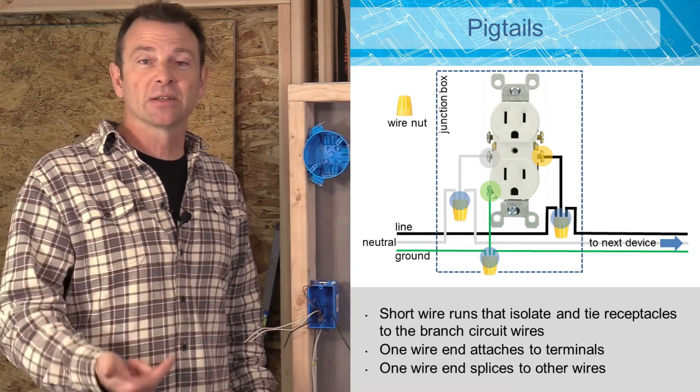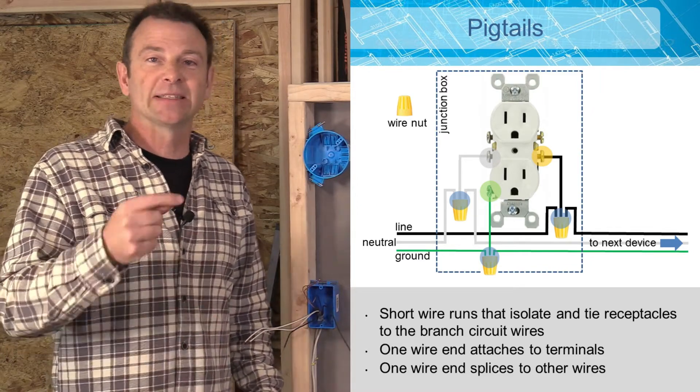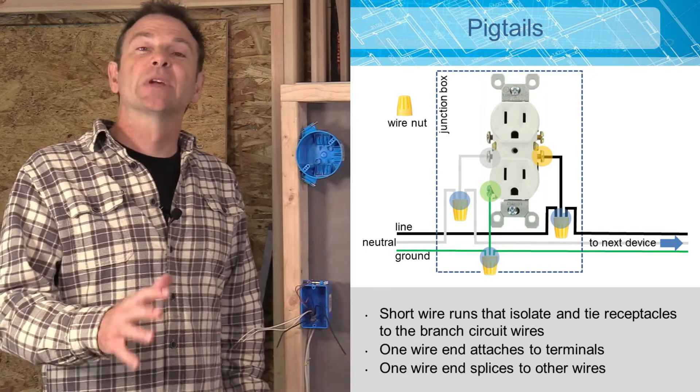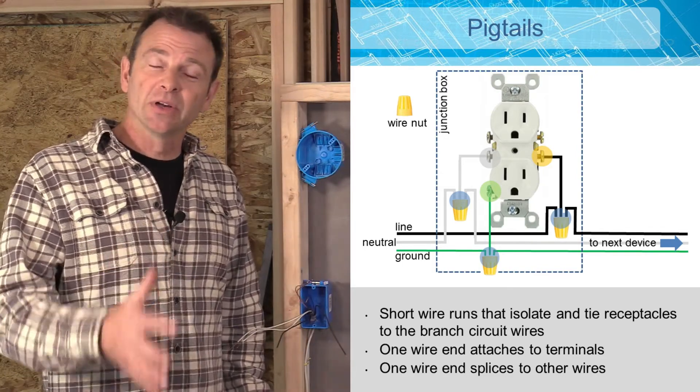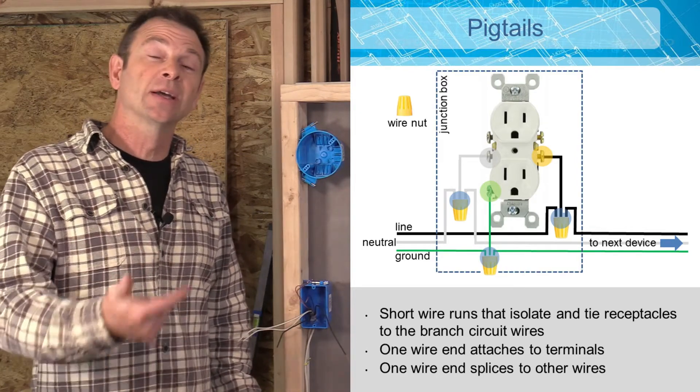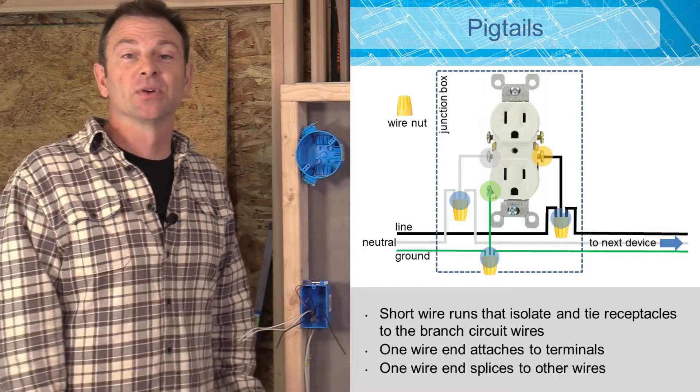This is a perfect solution for making a multi-wire connection to that single terminal. You never want more than one wire wrapped around that terminal. It's really good to learn your schematics. The more you look at it, the more it will make sense. And I'm going to leave this up while we're doing our wiring for this outlet so it will help reinforce all of this.